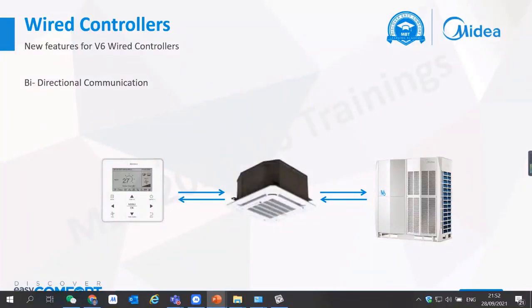Suppose you have a unidirectional communication, maybe V5X generation or the V4 plus generation. So you set the temperature 26 degree in the wired controller, and you send it. Okay, so the wired controller will display 26 degree and unit will display 26 degree. Now I will use a central controller or maybe a remote controller to change the temperature to 21 degree.